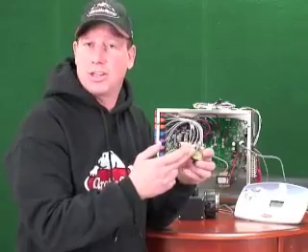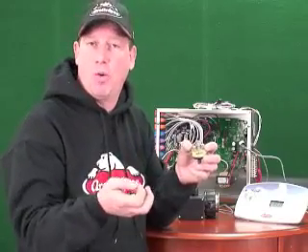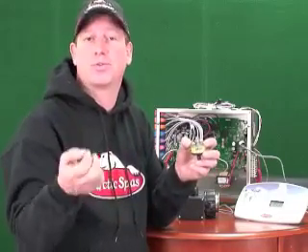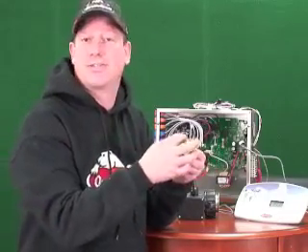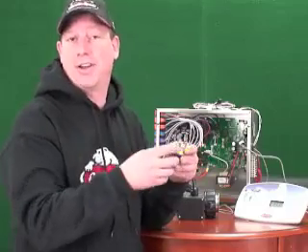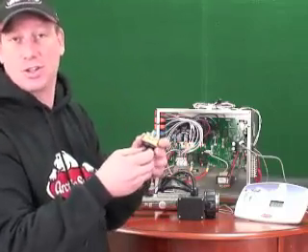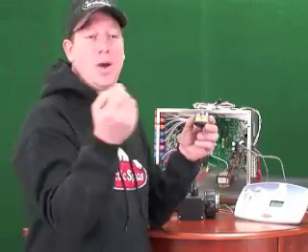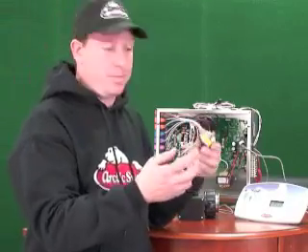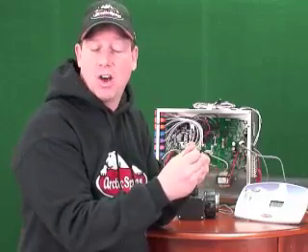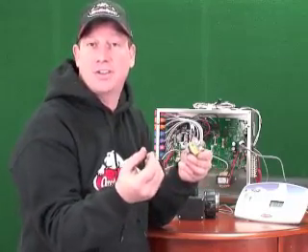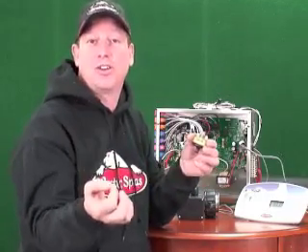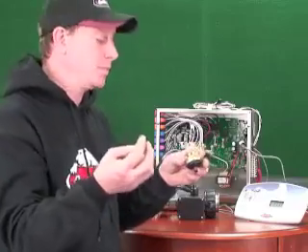If it does not close the contact, you're going to get an FLO, which means flow switch open because the contacts have not closed. Obviously FLC, flow switch closed, is the opposite. If the pump is not running but the diaphragm is closing the contact, you're going to get FLC which means it's closed when it's not supposed to be.